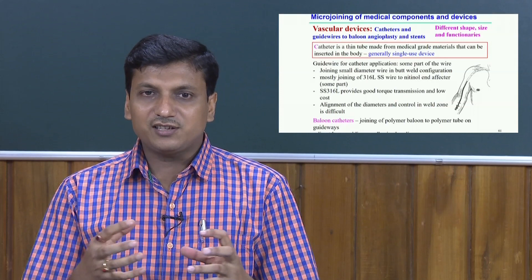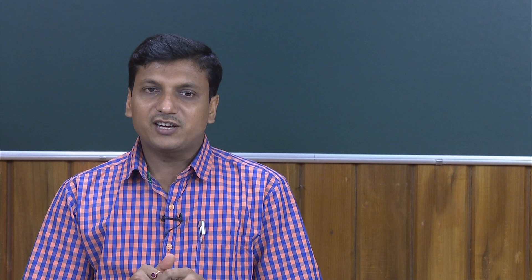The stent is a permanent implant. Stents are typically produced by laser cutting from a tube and welded onto a small wire. The objective is that the stent, in collapsed form, is delivered to a very precise location. Challenges include achieving excellent surface finish and edge finish, control of the heat affected zone, and extreme control of orientation and the laser cutting path.